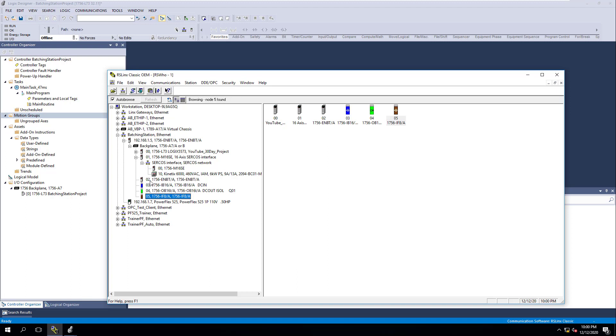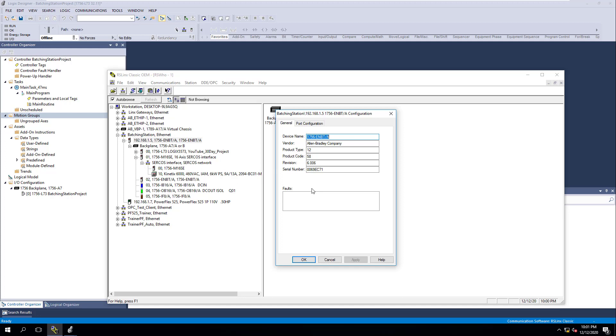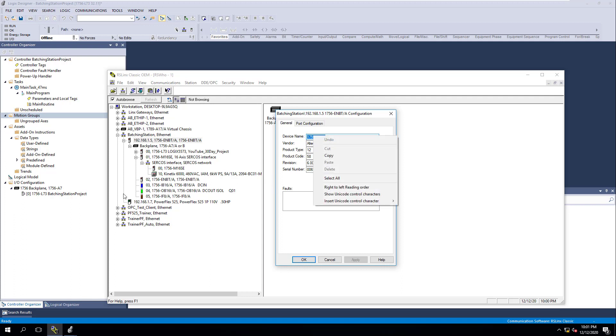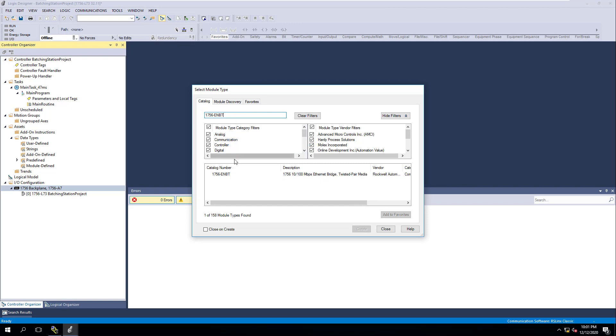First, we know our Ethernet card is right here — our 1756-ENBT. Now we can't right-click and go to that one; we have to come to the very top one because that is our actual communication path. What I like to do — just to kind of cheat — is go ahead and copy this. The quickest and easiest way is to copy this, then come over here to your backplane, select new module, and paste that in here and click it.